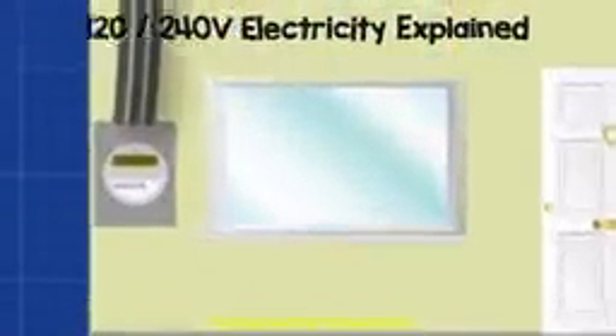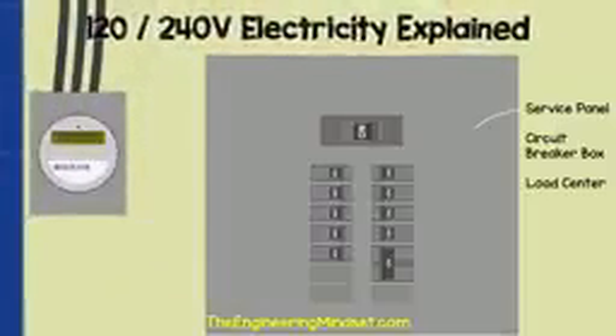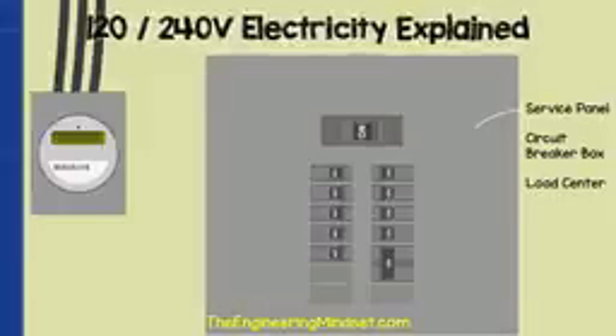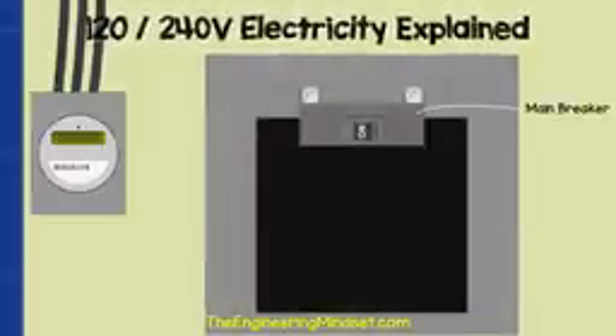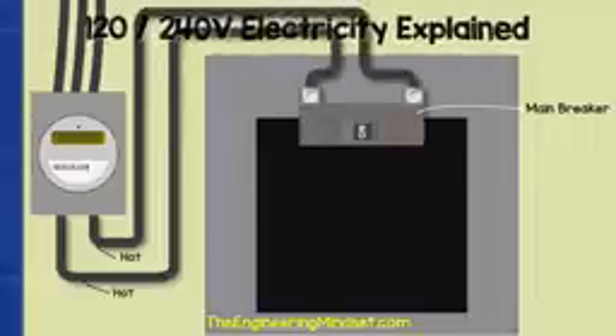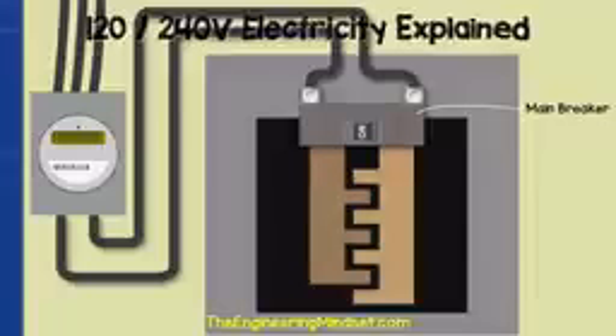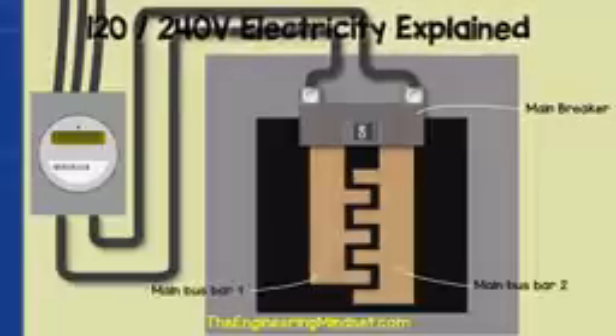So if we zoom into the property, we find a main service panel which is sometimes called a load center or breaker box. If we remove the cover and look inside, we first find the main breaker. This is usually at the top of the panel, but it might be at the bottom. The 2 hot wires from the electricity meter will connect directly to the lugs on the main breaker. Coming out of the main breaker will be 2 main bus bars.